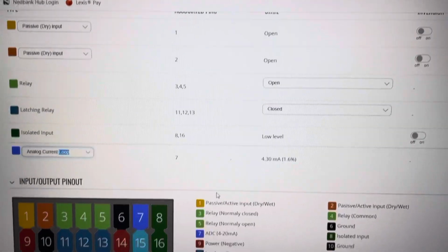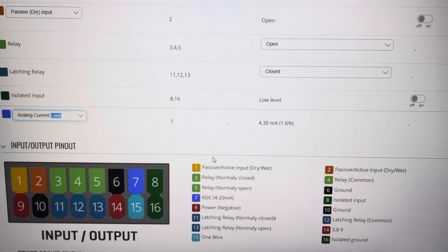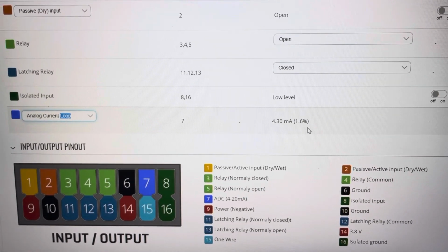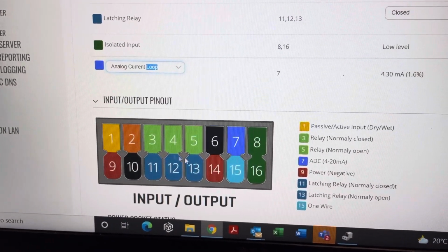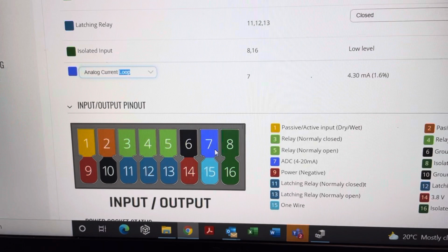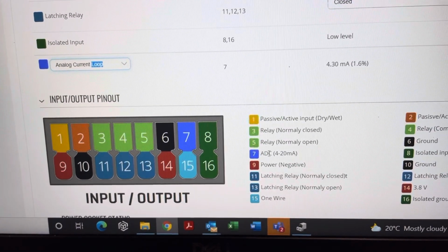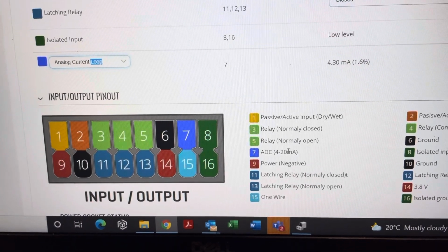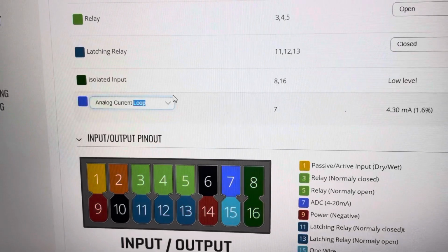Okay, this is a quick video of the 4 to 20 milliamp current input on the TRB. If you look here, there's all the pins for the TRB, all nicely color coded. Pin 7 is analog DC, 4 to 20 milliamps.